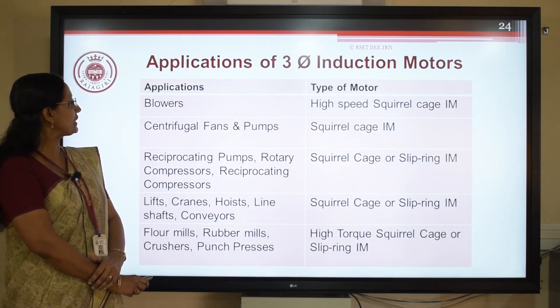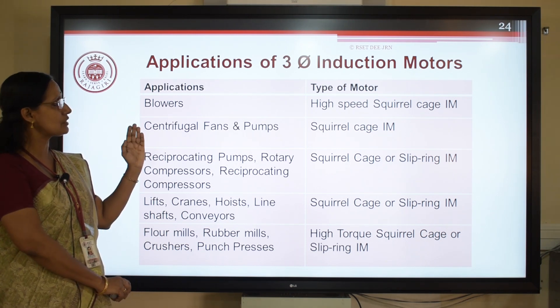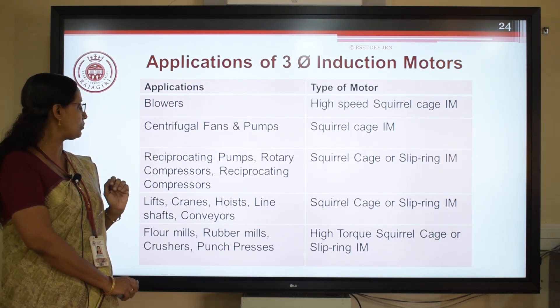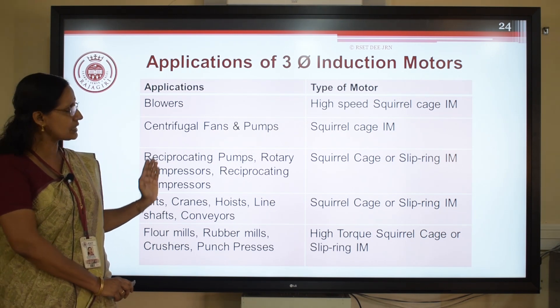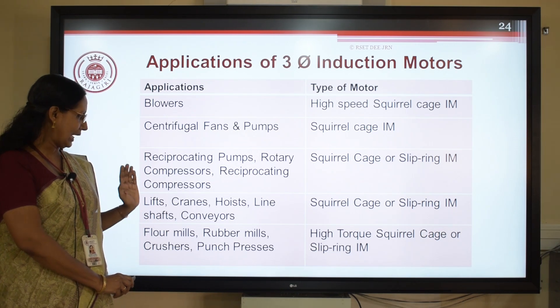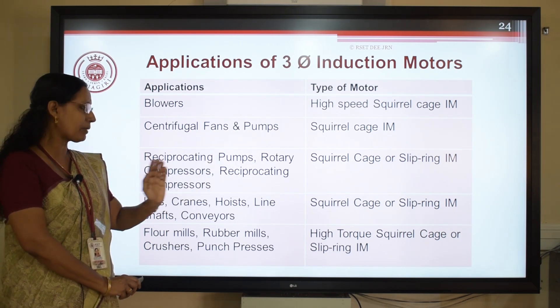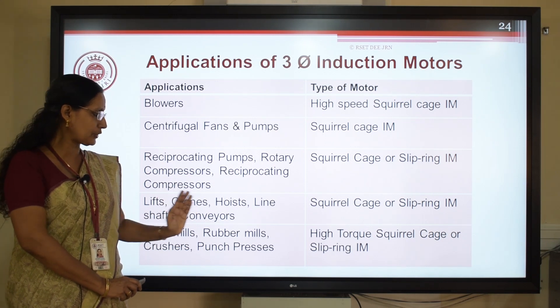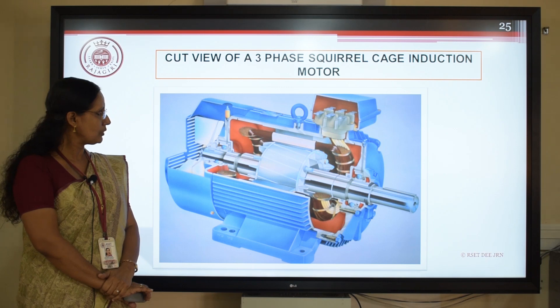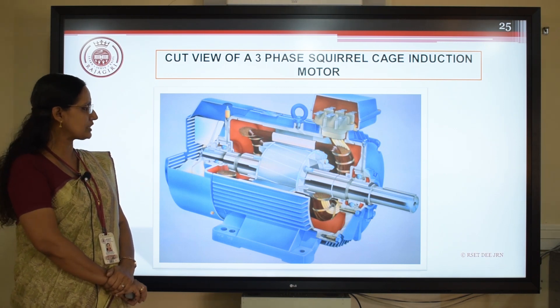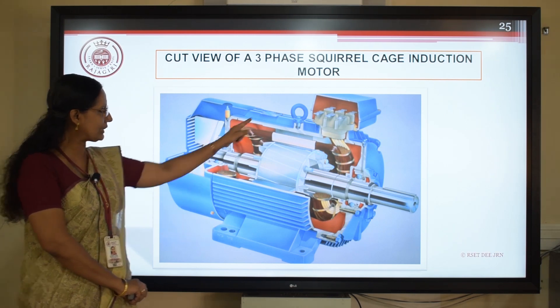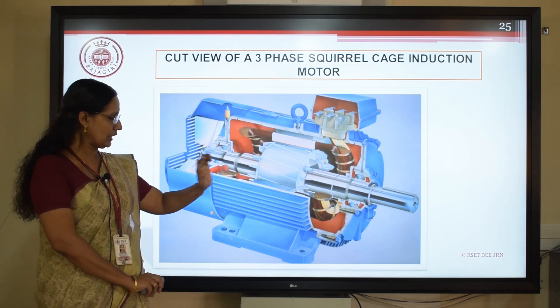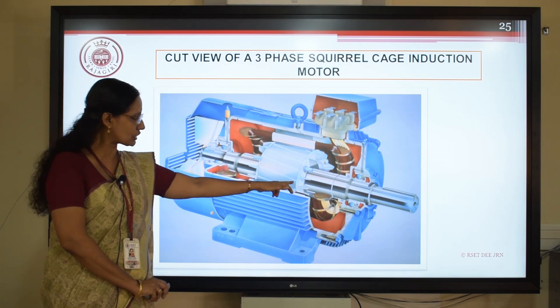Based on application, for blowers we go for high-speed squirrel cage induction motor; for centrifugal pumps and fans, generally squirrel cage induction motor; for reciprocating pumps, rotary compressors, reciprocating compressors, either squirrel cage or slip ring; for lifts, cranes, hoists, generally slip ring but squirrel cage can also be used; for flour mills, rubber mills, crushers, and punch presses, high-torque squirrel cage or slip ring. In the cut view of the squirrel cage induction motor, you can see the frame, foot, lifting eye, stator core with three-phase winding, terminal box, rotor, rotor shaft, rotor core with rotor bars short-circuited with end rings, and ball bearings.